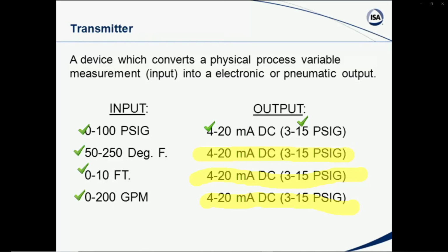But again, the output of these devices can be electronic, can be analog electronic, can be digital electronic, it can be pneumatic. These are the standard unit ranges that we have now. Sometime back we had pneumatic wars and we had electronic wars, just like we have some of the fieldbus wars today. But after all the smoke had cleared, the settlement came out at 4 to 20 milliamps or 3 to 15 pounds. Of course, now we have digital signals.